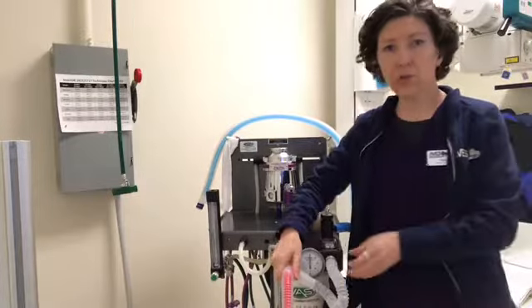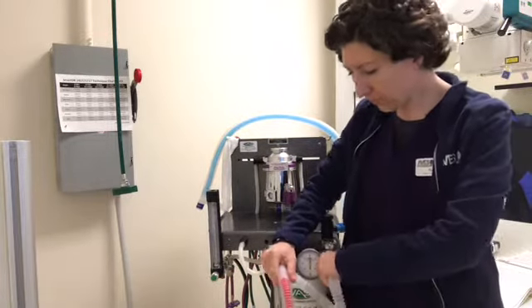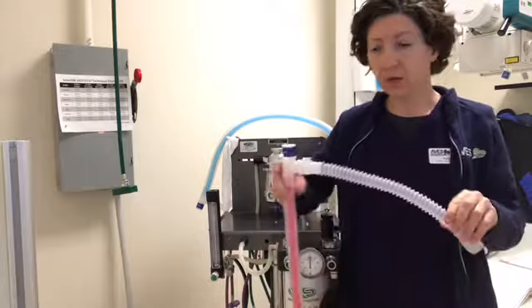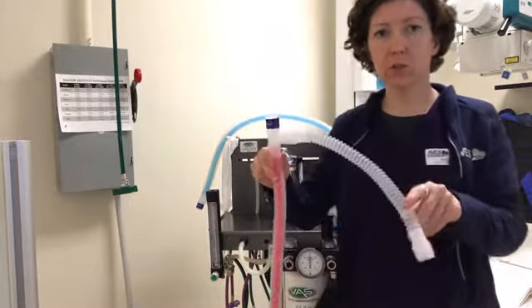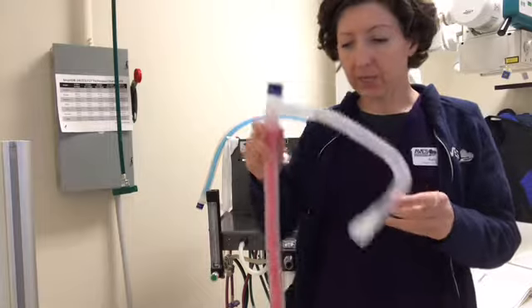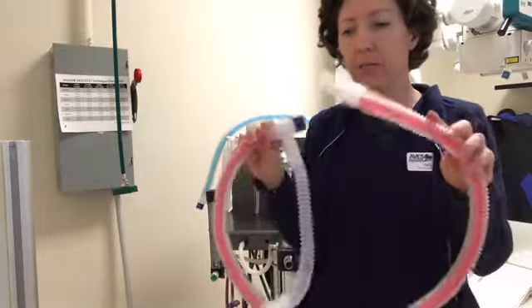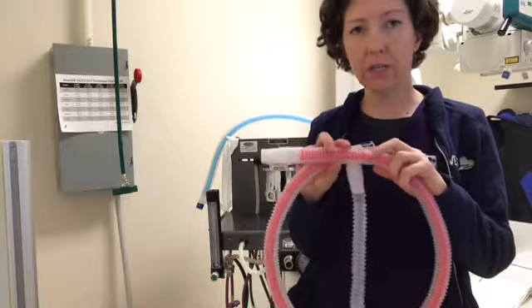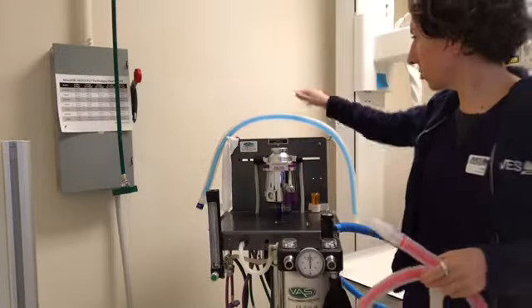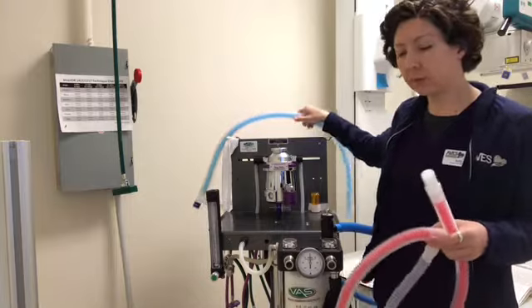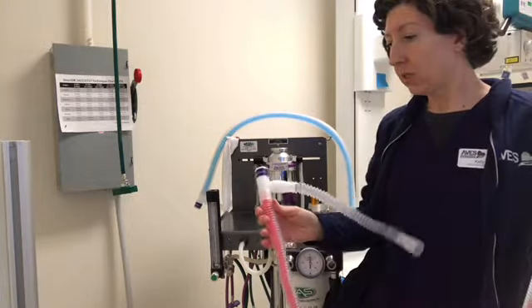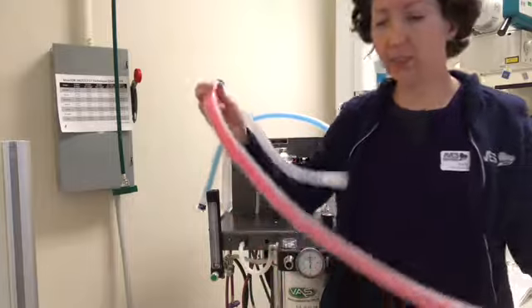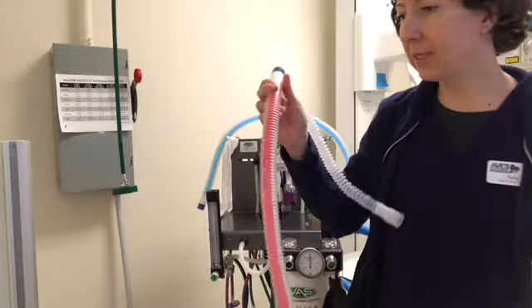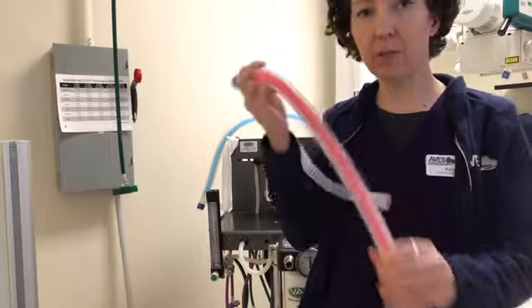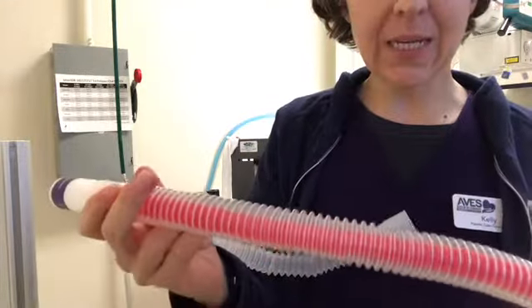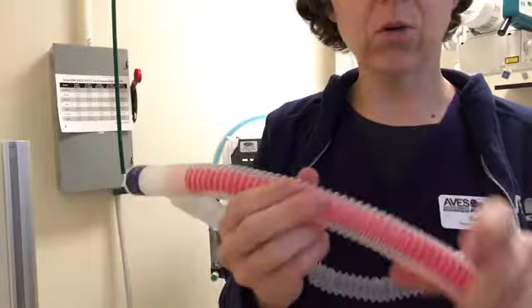Okay, so what I'm going to go over now is the rebreathing system. This is what you call a universal F circuit. This size here, this pink tubing, is for patients under 7 kilograms. This larger tubing is for greater than 7 kilograms. So essentially this is a tube within a tube. The inspiratory tube is this pink tubing on the inside. The expiratory tube is this clear tubing around it.